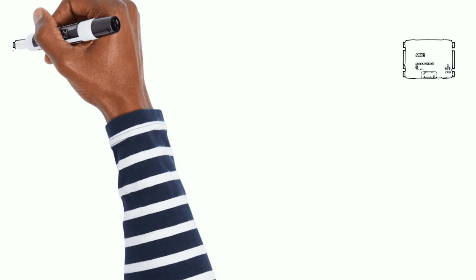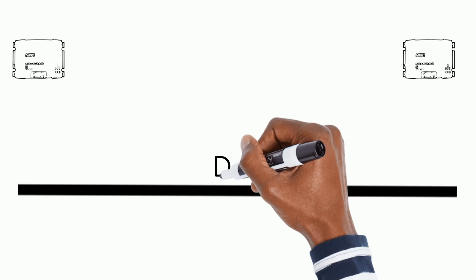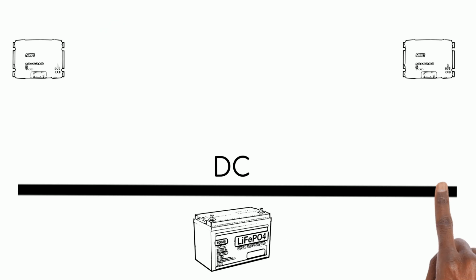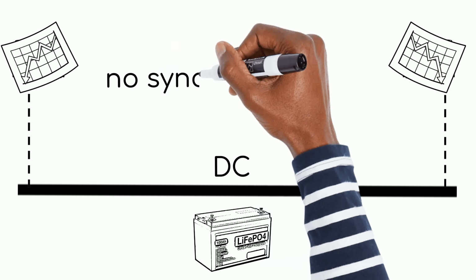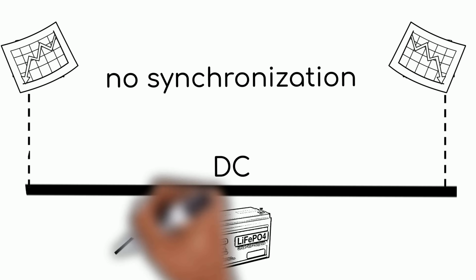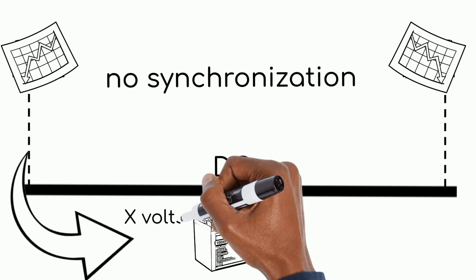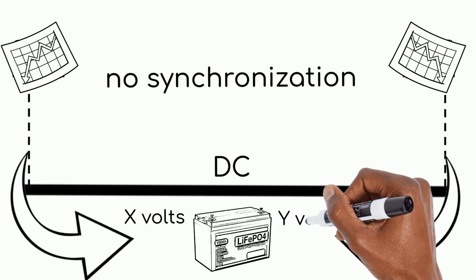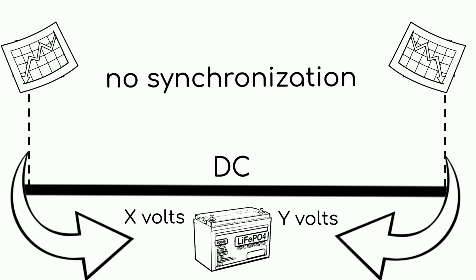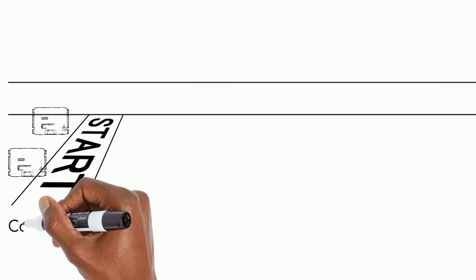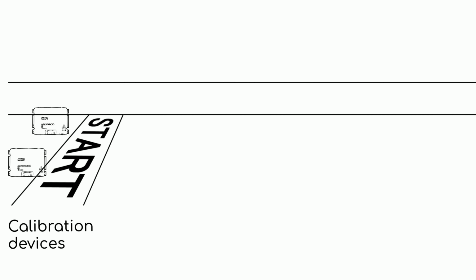If independent chargers are not synchronized, then each charger operates according to its own internal program. And even if the settings indicate the same voltage values for switching to absorption and float modes, the chargers can actually work differently. Why does this happen? Calibration for all devices is at least slightly different.